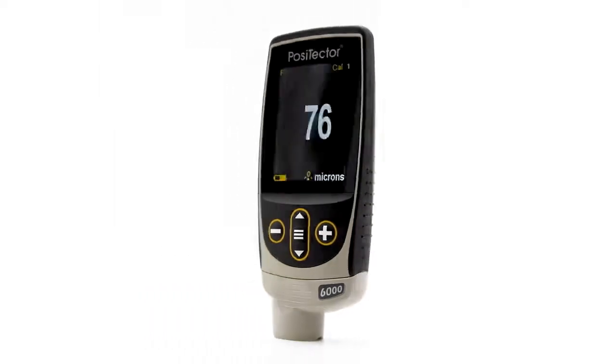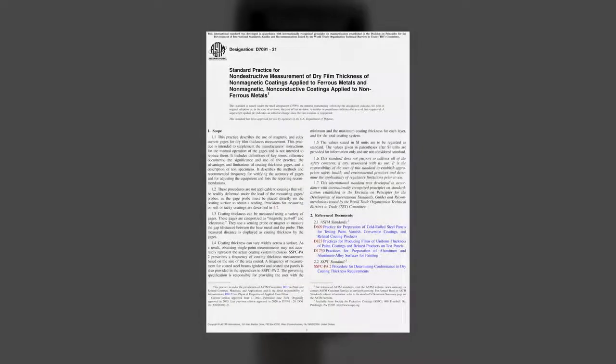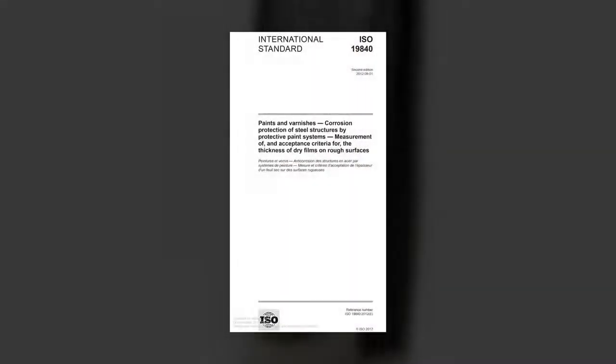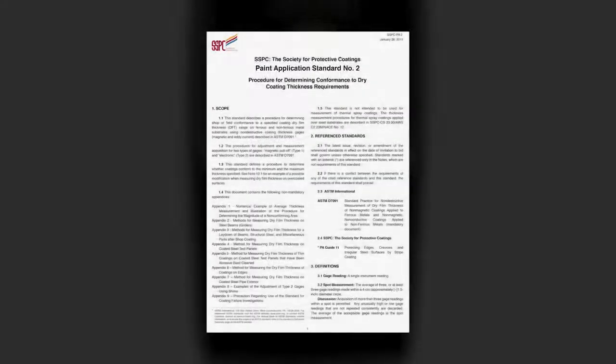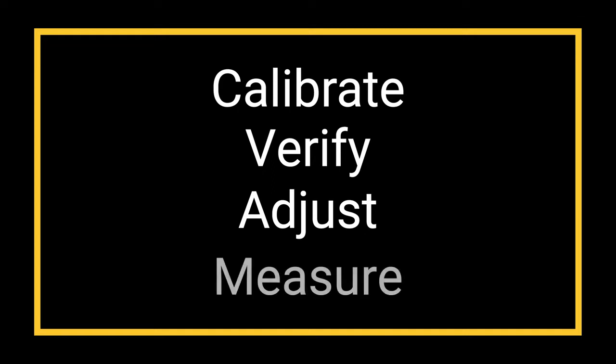Taking a dry film thickness measurement with the PosiTector 6000 is simple. Standards such as ASTM D7091, ISO 19840, and SSPC PA2 describe the following four operational steps for all coating thickness gauges: calibrate, verify, adjust, and measure.